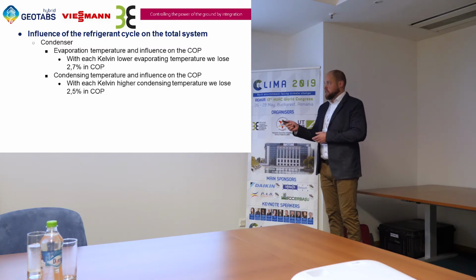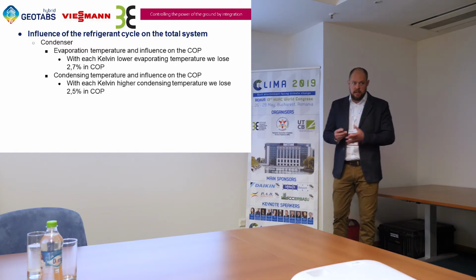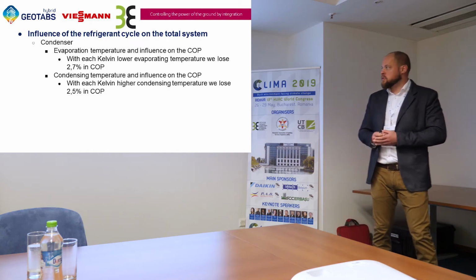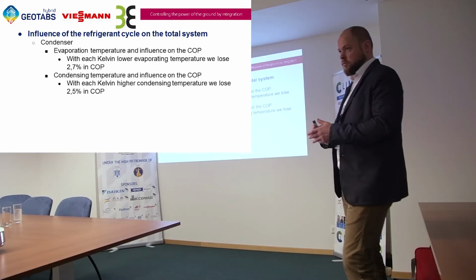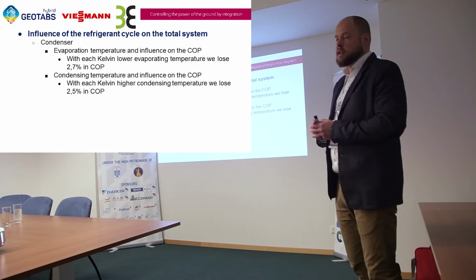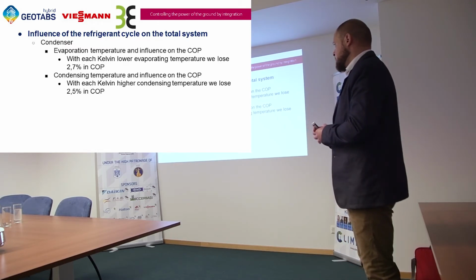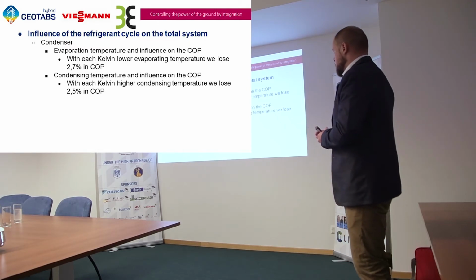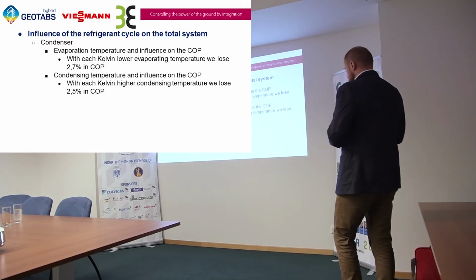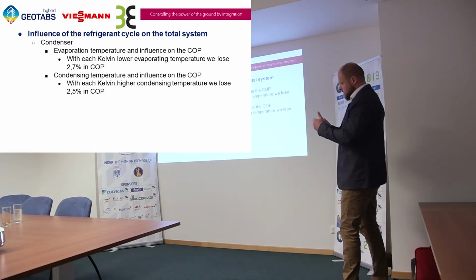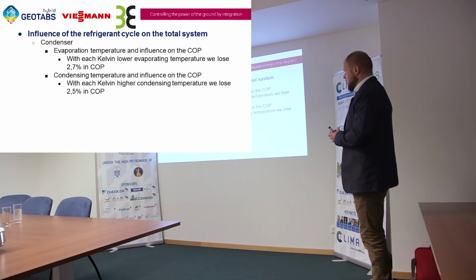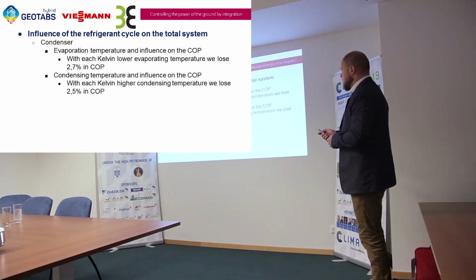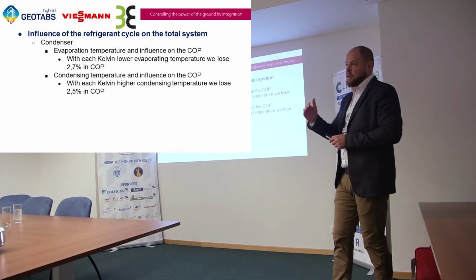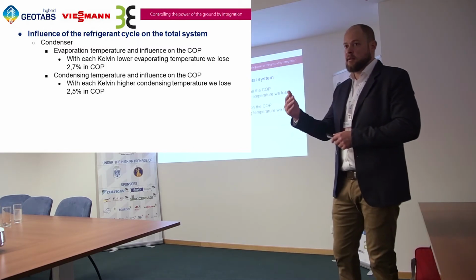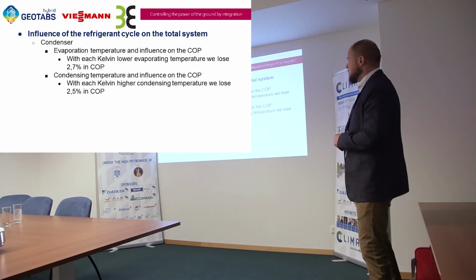We can see here at the evaporation temperature, when we have a difference of 1 degree or 1 Kelvin, we have a gain of about 2.7% in COP. For example, you can call that a rule of thumb. On the condensing side, it's a little less. When we can reduce the departing temperature in the condenser, we gain about 2.5% in COP. So that means when we have a temperature that's 10 degrees higher than necessary, we lose about 25% of efficiency of the system.